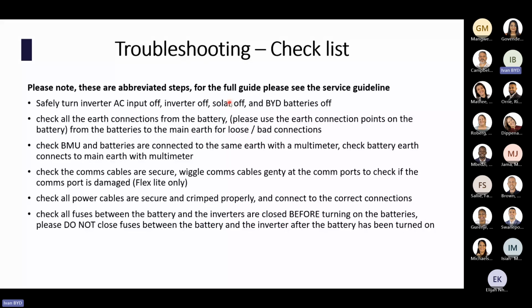So in terms of troubleshooting, if there is an issue, please safely turn off the AC input, the inverter, the solar, and the BYD batteries. Check all the earth connections from the battery. Check the BMU and the batteries are connected to the same earth with the multimeter, just buzz it through. And check the comms cables are secure. Wiggle the comm cables gently just to check everything's fine.